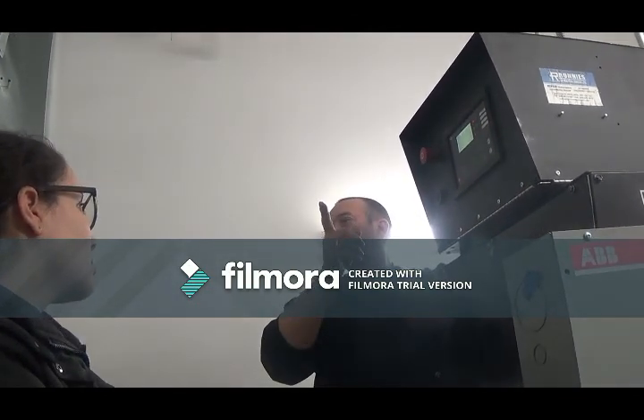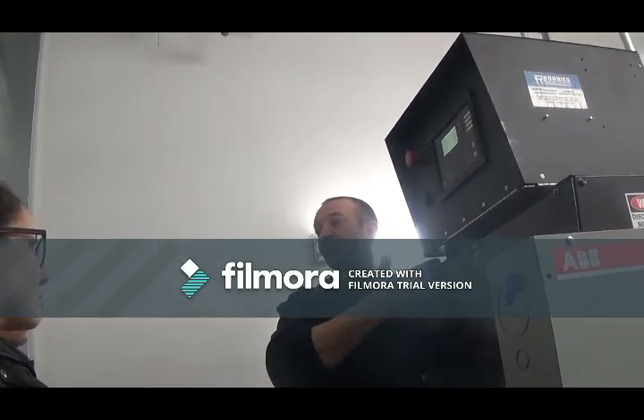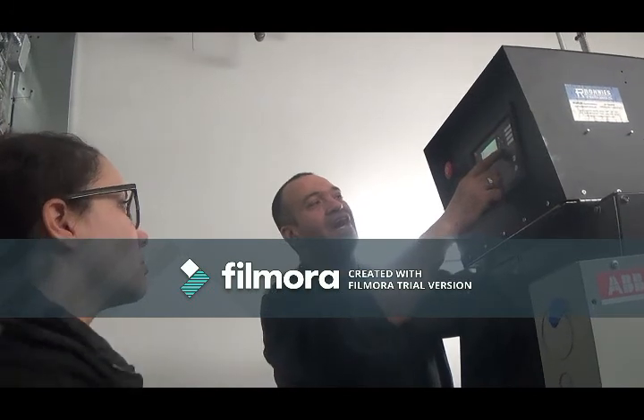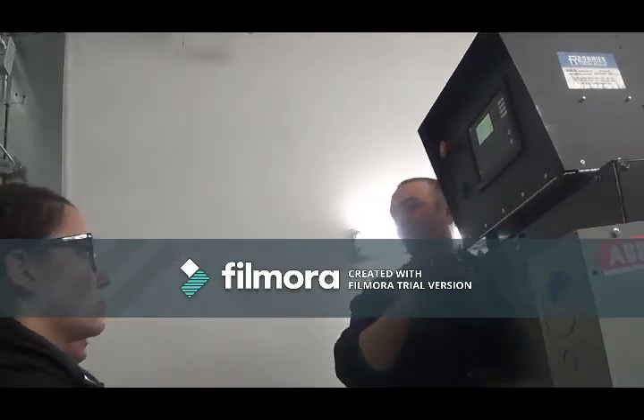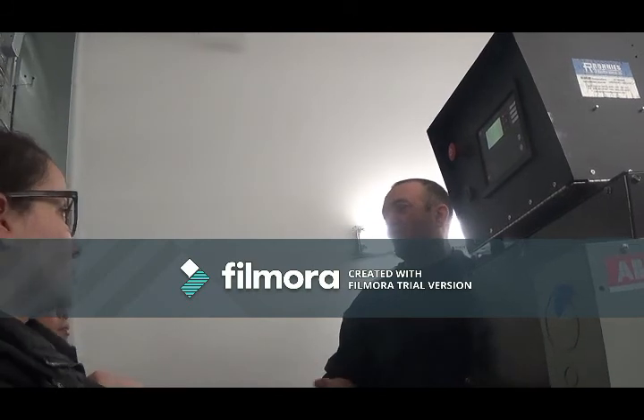If you see 210, 215, but it's not shutting off, maybe a sensor is not reading. Like they say, computers can make a mistake. The brain never makes a mistake. Current, that's your amperage. Only when you do a transfer will you have current in this thing. If you don't do a transfer, you'll have voltage, but you will have no amperage.